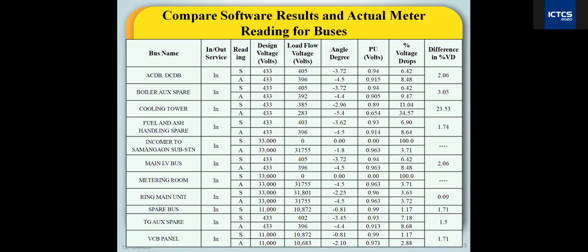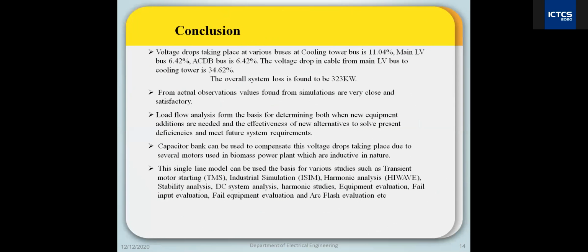Likewise, I have done the study for the whole plant, and in the end I found that the voltage drop taking place at various buses: at the cooling tower it is 11.04%, which we have to reduce. The main LV transformer, low voltage transformer, it is 6.42%. ACDB is 6.42%, and the voltage drop in the cable from the main LV bus to the cooling tower is 34.62%.